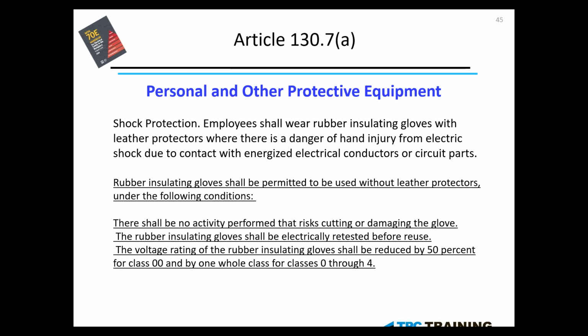This is an update I wanted to bring to your attention today. Shock protection. Employees shall wear rubber insulating gloves with leather protectors where there is a danger of hand injury from electric shock due to contact with energized parts. So real quickly, without spending too much time on it, as we'll cover it next month, this is the section that they're allowing us now to wear our rubber gloves without leather protectors if we can meet all three of the criteria below, and that is found in 130.7A.